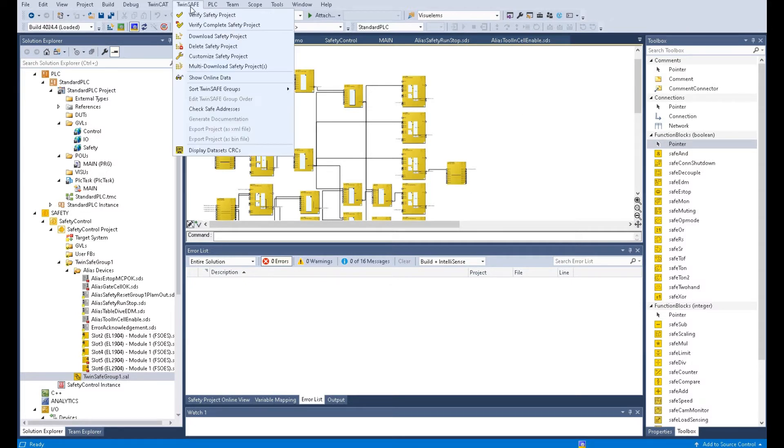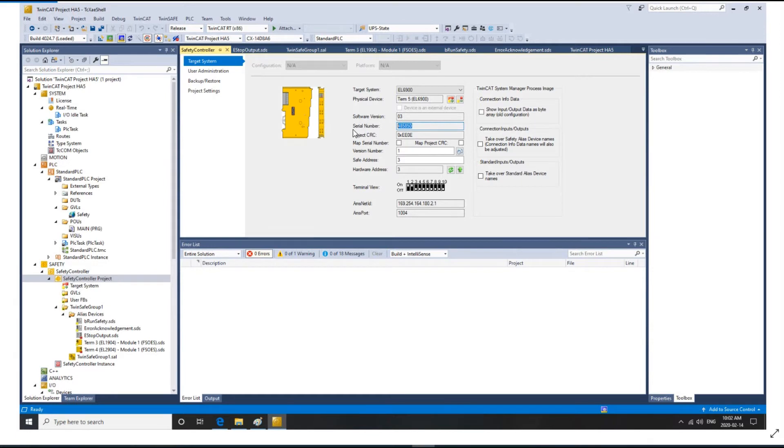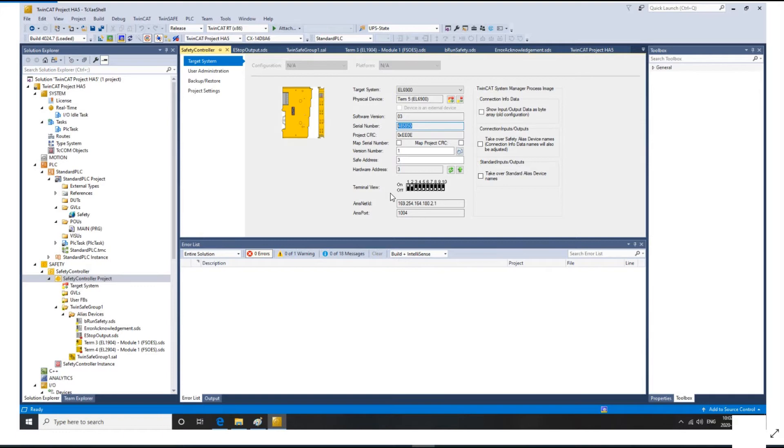After that, click TwinSafe, click download safety project. Because we already read this hardware address, after the offline program reads the online configuration, you will see the software version, serial number, as well as the safety address. The safe address and the hardware address DIP switch must match together. When you click download, the system will pop up this page.